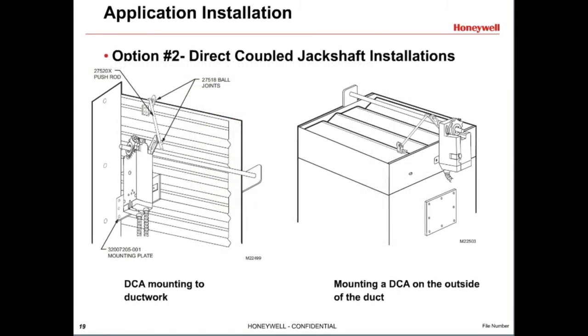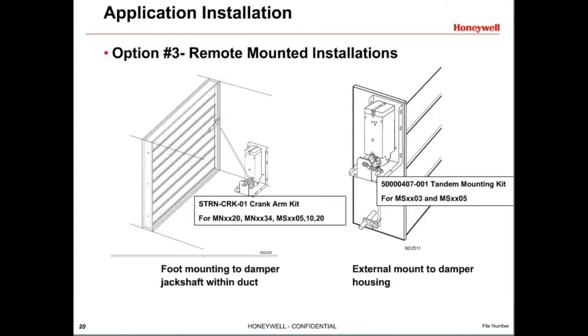Other mounting methods, such as using a jack shaft, are also common. Here are 2 methods to mount DCAs onto jack shafts. Jack shafts on Honeywell dampers are 1-inch diameter. Be sure to order an actuator that accepts this shaft size. The third method of installing a damper is foot-mounted. Use a foot mounting kit to install the actuator remote from the damper, and a jack shaft to connect the actuator to the dampers. This is commonly used to replace old foot-mounted actuators.